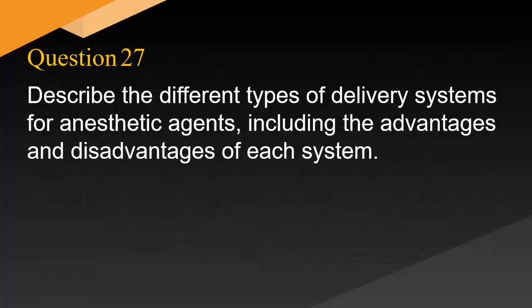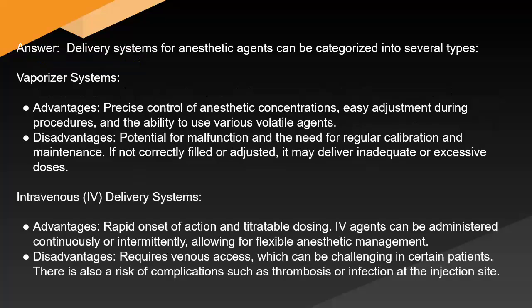Describe the different types of delivery systems for anesthetic agents, including the advantages and disadvantages of each system. Answer: Delivery systems for anesthetic agents can be categorized into several types. Vaporizer systems. Advantages: precise control of anesthetic concentrations, easy adjustment during procedures, and the ability to use various volatile agents. Disadvantages: potential for malfunction and the need for regular calibration and maintenance. If not correctly filled or adjusted, it may deliver inadequate or excessive doses.